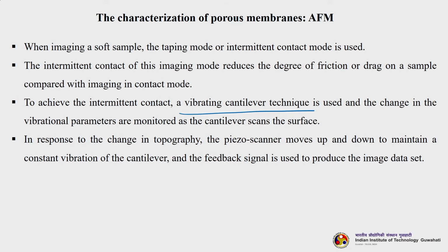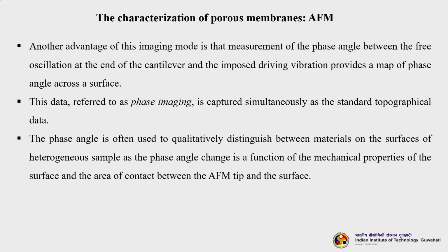So, in this technique the cantilever is vibrating, and changes in its vibrational parameters are monitored as the cantilever scans the surface. In response to change in topography, the piezo scanner moves up and down to maintain a constant vibration of the cantilever, and the feedback signal is used to produce the image.